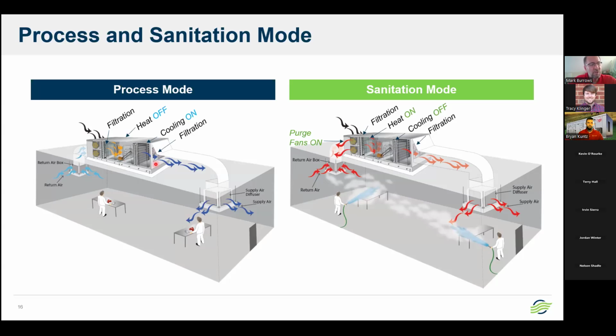If a customer chooses to take those filters out, what happens to the static pressure? Static pressure goes down, CFM goes up. That's exactly why in the one photograph that we showed, they had that sock material on the diffuser. Why? The filters are missing. Now this unit is delivering a lot more air at a higher face velocity. Therefore, there's issues with that. So just keep that in mind. It's critical that these have all the filters in place so we can manage the airflow going into these plants.